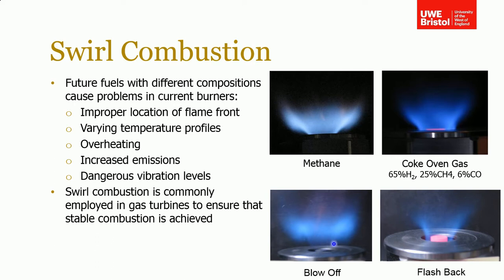The opposite is also a problem: if you change to a gas with slower burning characteristics, the flame can blow off — the bulk velocity of the fluid through the burner is higher than the burning velocity, so the flame lifts off, can't sustain combustion, and goes out. In a gas turbine, especially in aviation, that's obviously bad news. All these things need to be taken into account when looking at fuel, and the challenge now is to develop flexi-fuel burners that can run on quite a range of fuel compositions.